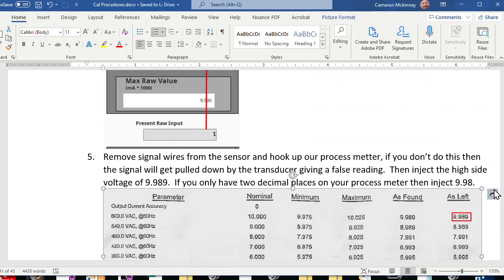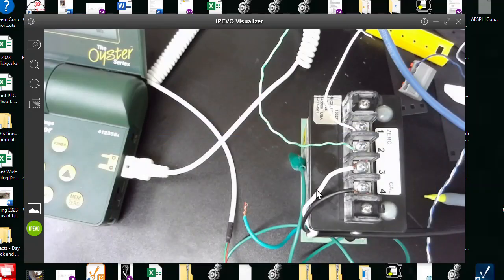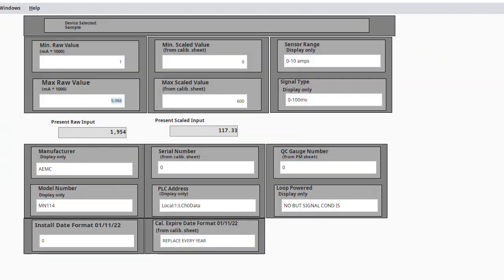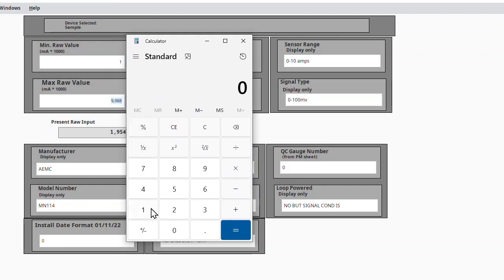So you would take 1% of what that says, which is 117. So we'll take 117 volts times 0.01 for 1%. That means I can have a plus or minus at that voltage range. So I can have 118.17, or I can have 116, whatever. You would add for the high side, and then you would subtract for the low side from 117, and that's what your voltage should read on your electrical meter.